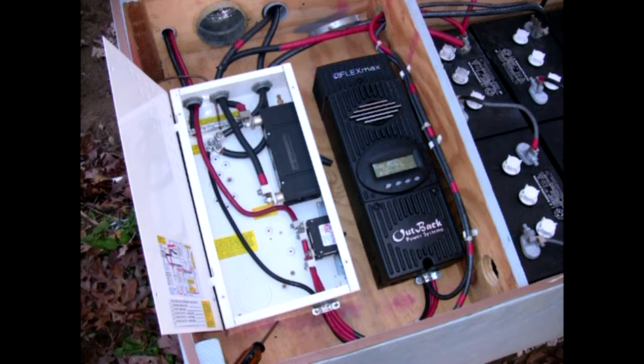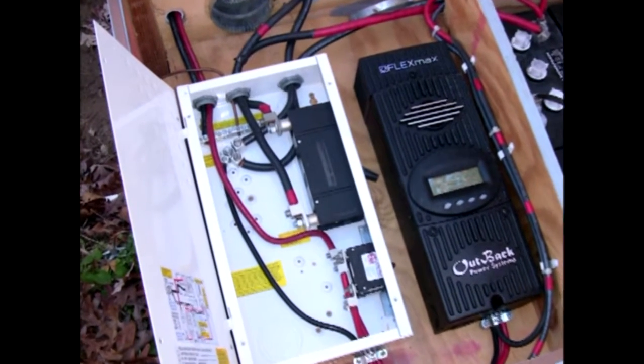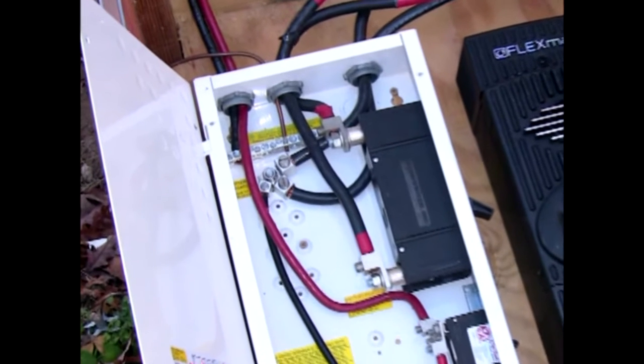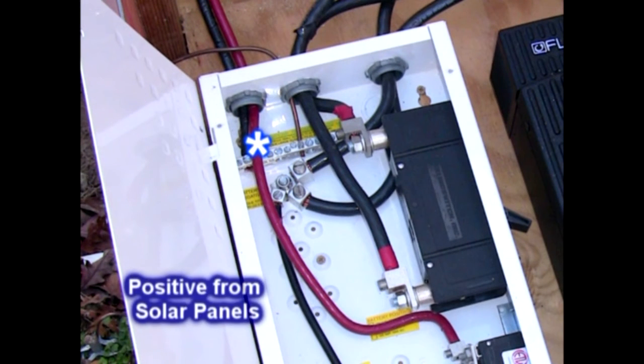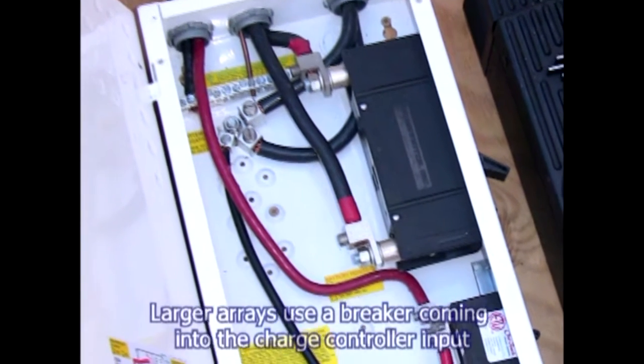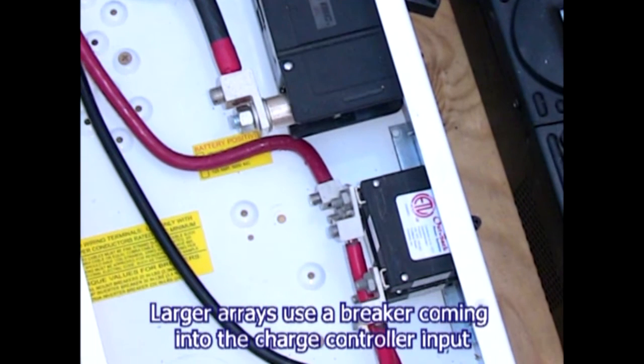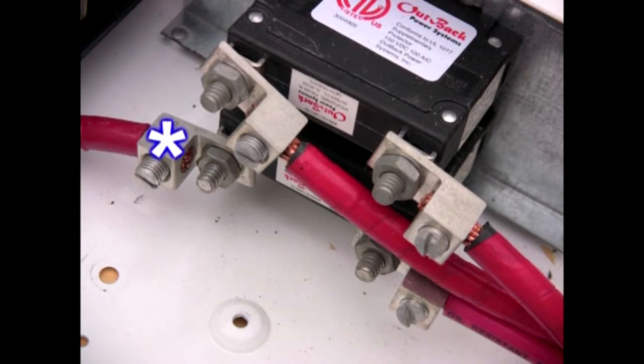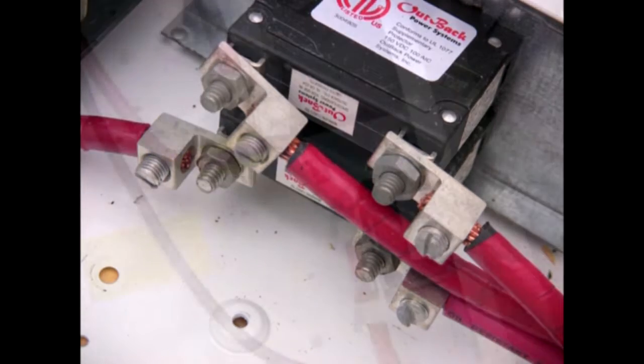So let's take a look in this system and see how our wiring is routed in from the panels to the circuit breaker box, and then the charge controller and our batteries, how they're all tied together. So we start at the top left where we can see the red wire coming in. It's a little bit smaller than the larger wire to the right, but it is the power coming in from the solar panels. And it goes down and is hooked to one of the two 90-amp breakers. Down here, this is the disconnect breaker that turns power off coming in from the panels and also gives it some protection, being a circuit breaker.